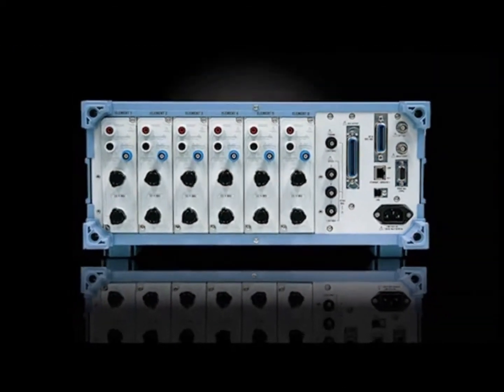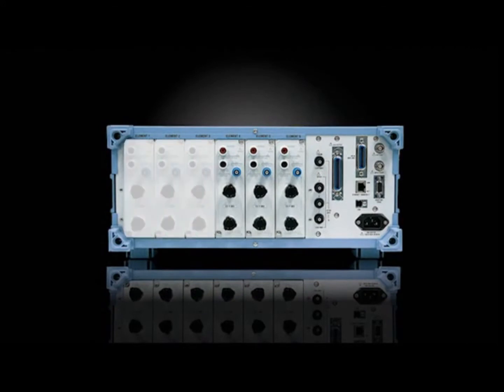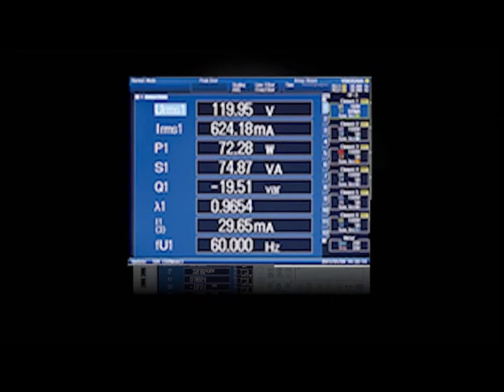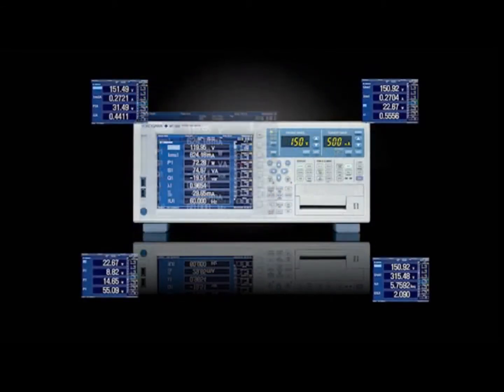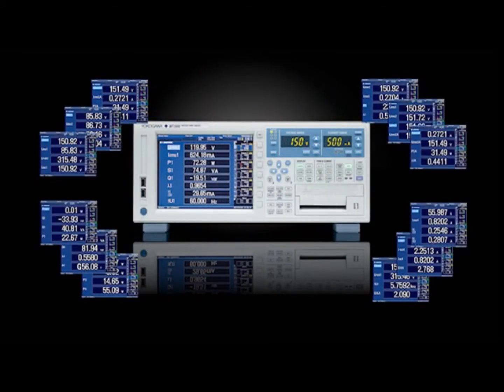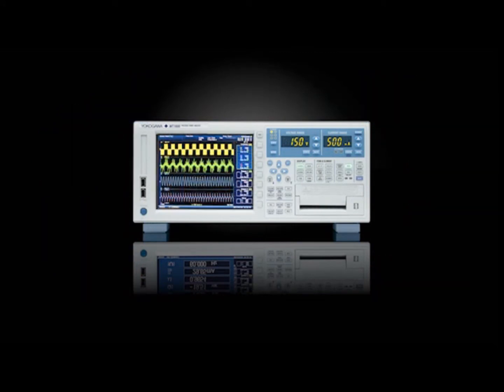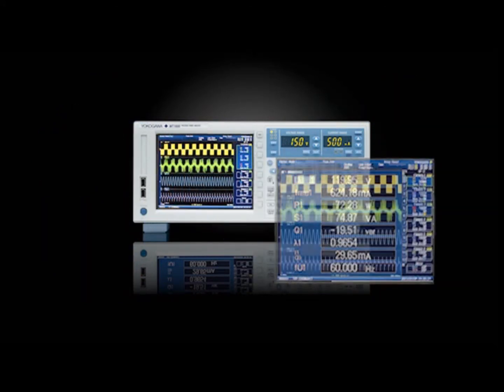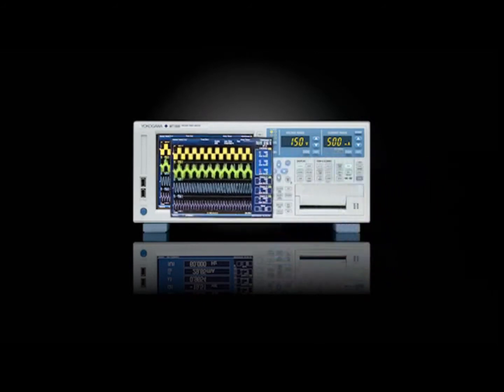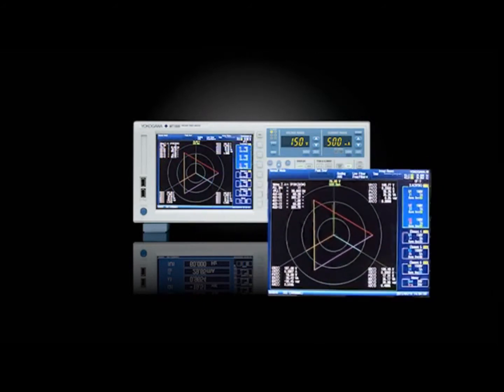conversion devices. The WT1800 is capable of performing up to 6 power input measurements, which makes it possible to perform efficiency tests between the input and output of products such as inverters. With its high-resolution 8.4-inch XGA display, it is simple to set up and display up to 12 different pages of measurement items in formats such as numeric, waveforms, and trends. A vector display is also available for voltage and current phase analysis.